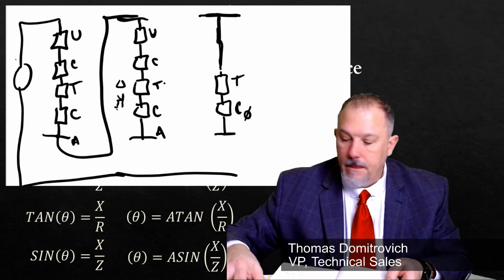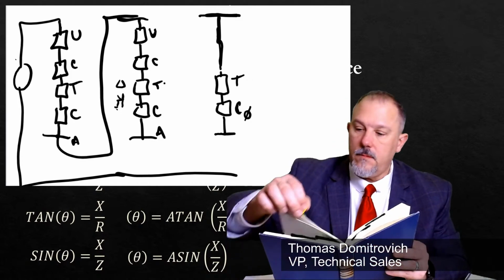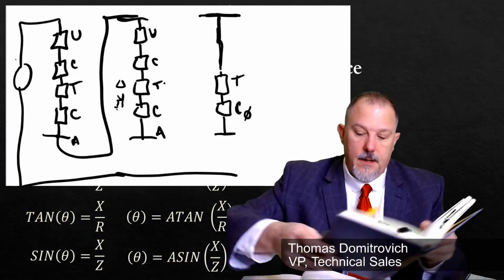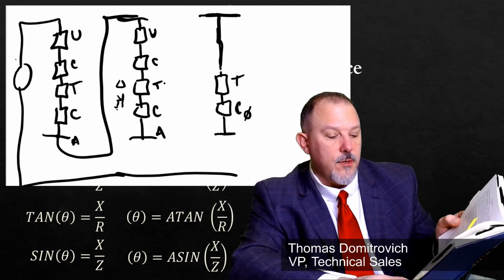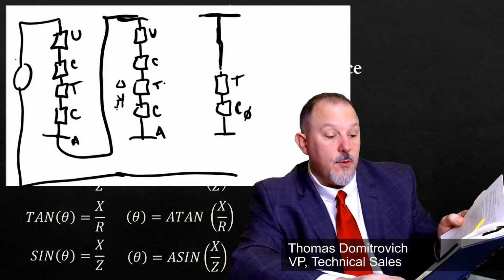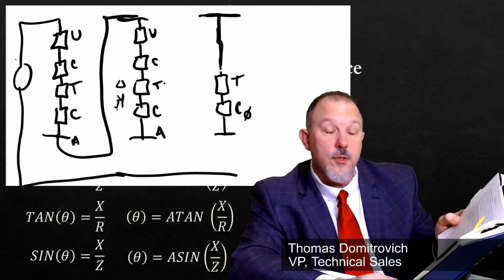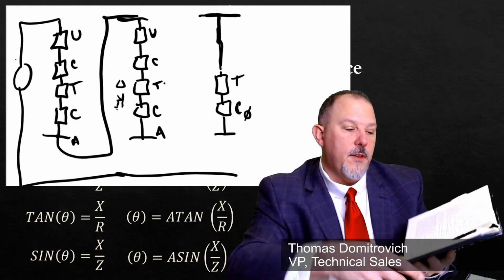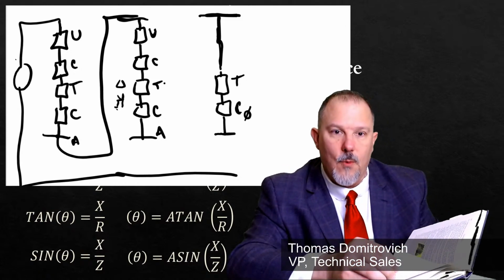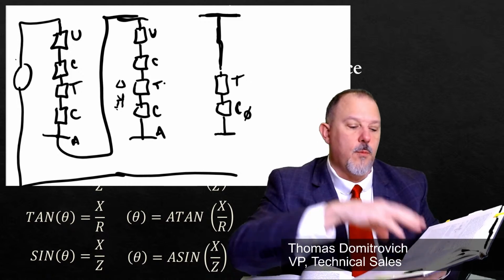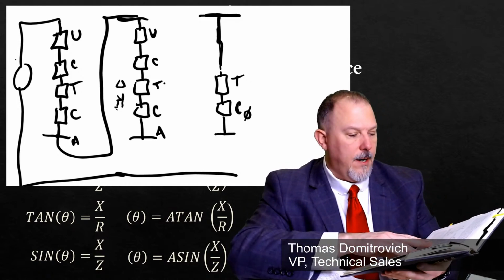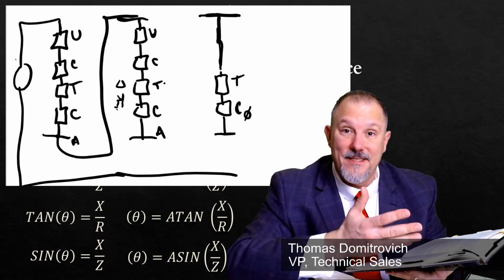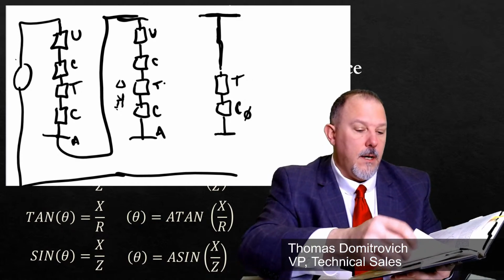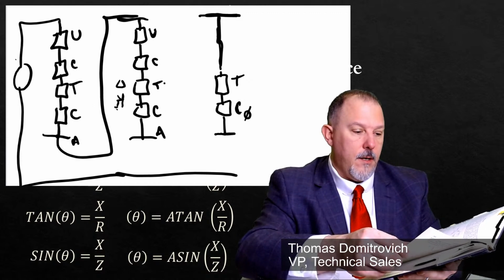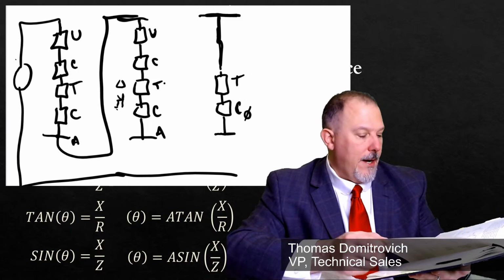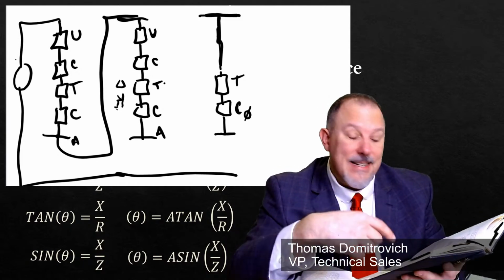So if I tabbed this for this discussion, this says that if the secondaries of the transformers are short-circuited, blah, blah, blah, the zero sequence impedance is then simply the conventional short circuit impedance. So they go through all the different configurations. They go through a delta Y ground configuration. They go to a YY transformer. They go to a Y grounded Y. They go to, you wouldn't do a delta delta, I mean, it wouldn't make sense. In any case, they go through, what is this? The YY auto transformer. They go through a grounding, a zigzag transformer.